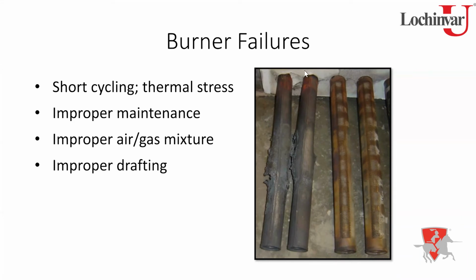Now, as far as the thermal stressing, it causes them. You've also got burners overheating. Primarily the reason for burners to overheat would be dirt, right? As your fan's running, whatever's in the air, that fan's going to pull in, it's going to end up in the burners. Your burner is the ultimate filter. So as those burner ports start to get plugged up with dust, dirt, lint, whatever, basically then you're reducing the amount of gas and air that can come through that port.